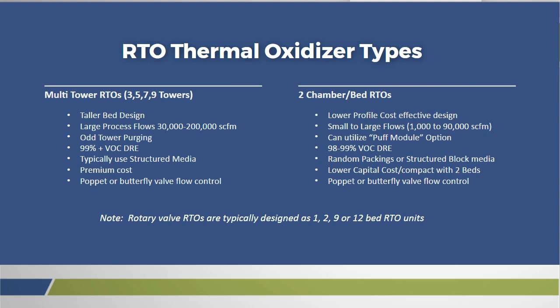We have the two bed on the right. It's generally a little bit more cost effective. It's for lower flow rates, generally speaking, compared to the larger, which tend to be larger multi-chamber RTOs. The two chamber is kind of limited to what you can ship easily, so generally 80, 90,000 SCFM. And it's generally standard rated at 98% destruction.